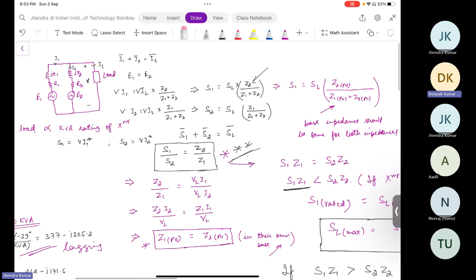Sir, in this case, if this condition is satisfied, we can connect 900 kVA load. Yes, you can connect it. If S1Z1 would have been equal to S2Z2, then you could have easily connected, sorry, 800 kVA. The load is 800 kVA, right? Sir, suppose we want to increase the load. If you want to increase it, then you have to check what will happen at that load.